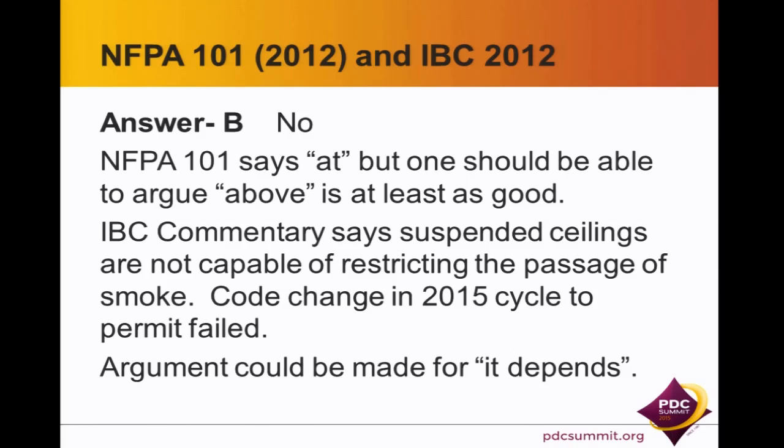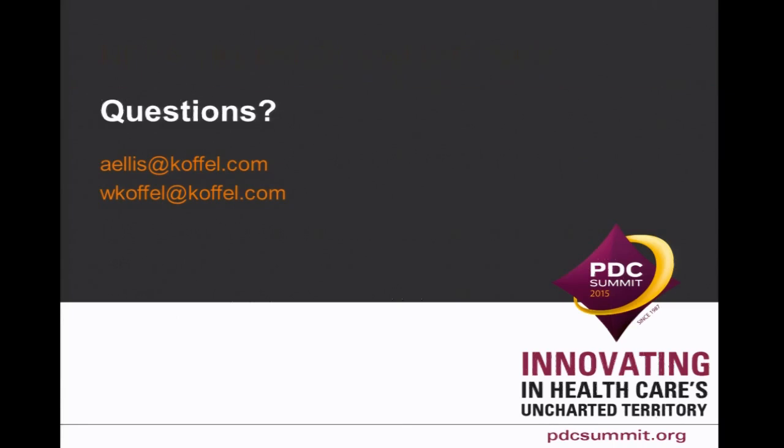And while you won't see any change in terminology in the IBC, I clearly have to interpret the IBC right now to say, if you have a lay-in acoustical tile, your corridors need to go all the way up. Until, hopefully, well, 2018 will take a little while to come out, but that is on the agenda for Memphis. So they have come back to re-look at this issue in the next code change cycle, and hopefully we will address that issue.